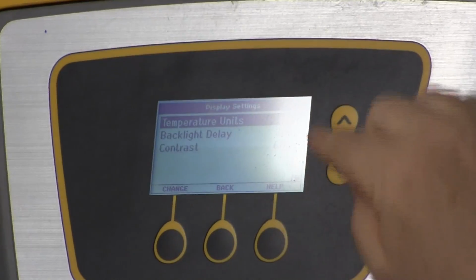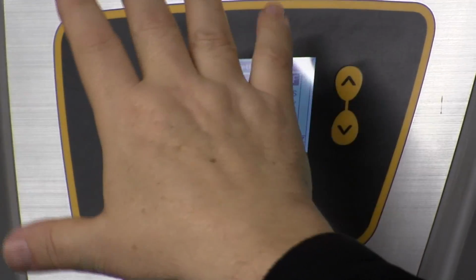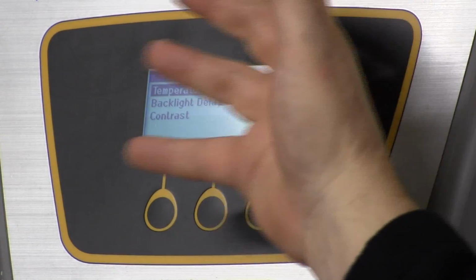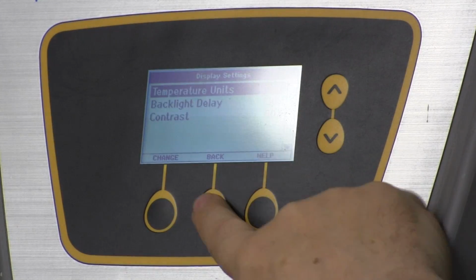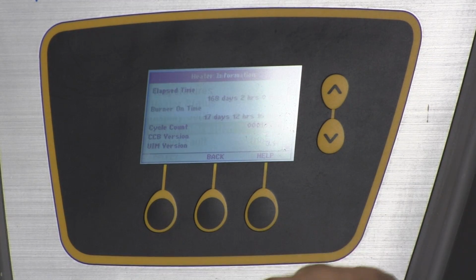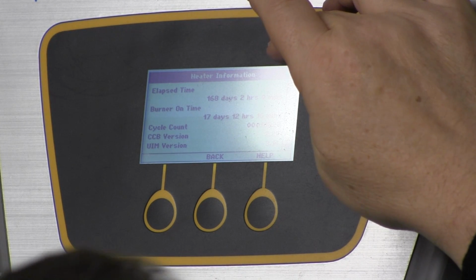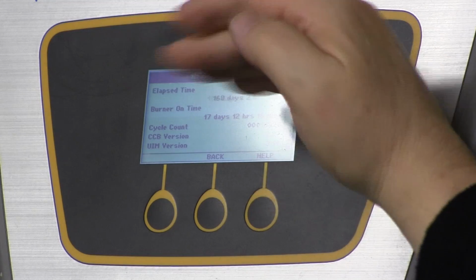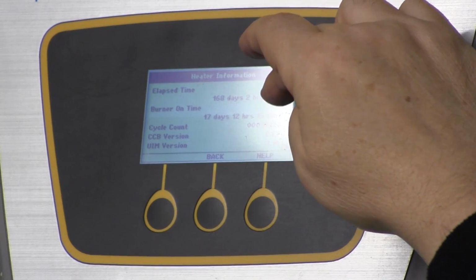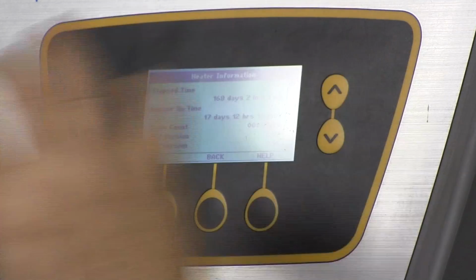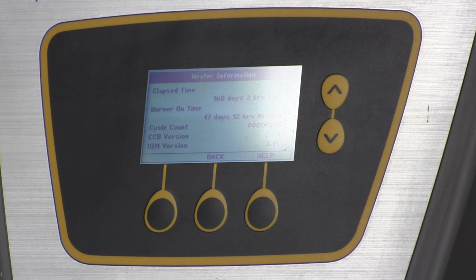Here's where you can change the display settings. You can change the contrast. You can put it in a different language. You could make the light go on all the time, or for energy savings have it go off. So you can play with that. Here is the heater information. This heater has actually been on for 168 days, 2 hours and 0 minutes. So it tells you how long the heater's been in operation. It also tells you the burner's been operating 17 days, 12 hours, and this heater has cycled 18,000 times. So you could look at this heater and that heater and see if they're operating the same. Check your cycle counts. You can get a good idea of how the heater is operating.